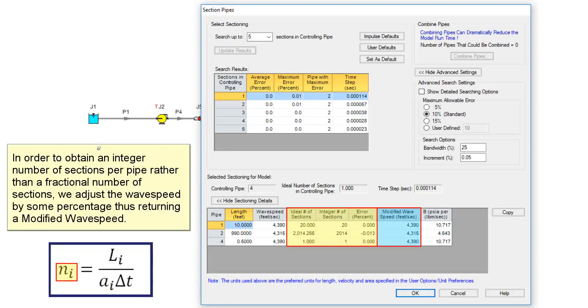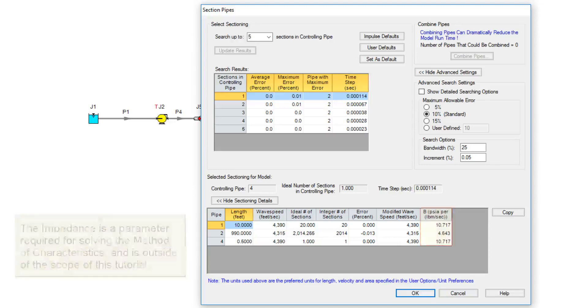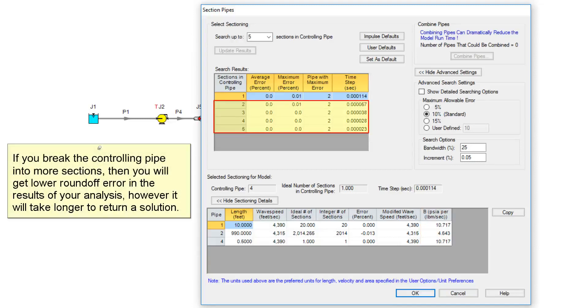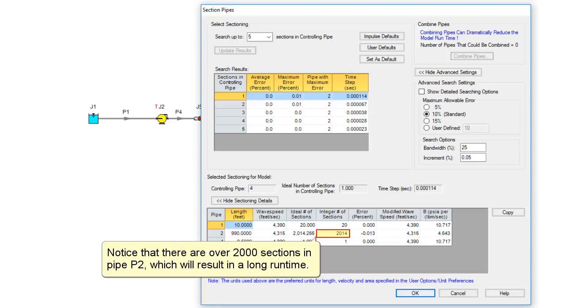In order to obtain an integer number of sections per pipe rather than a fractional number of sections, we adjust the wave speed by some percentage, thus returning a modified wave speed. The impedance is a parameter required for solving the method of characteristics and is outside the scope of this tutorial. If you break the controlling pipe into more sections, then you will get lower round-off error in the results of your analysis, however it will take longer to return a solution. Notice that there are over 2,000 sections in pipe P2 which will result in a long runtime.